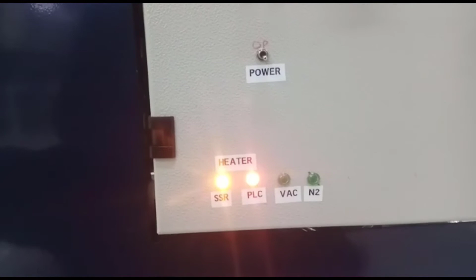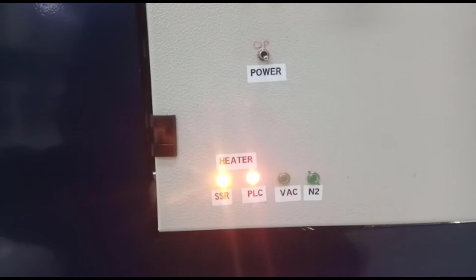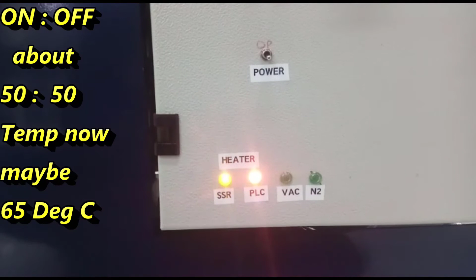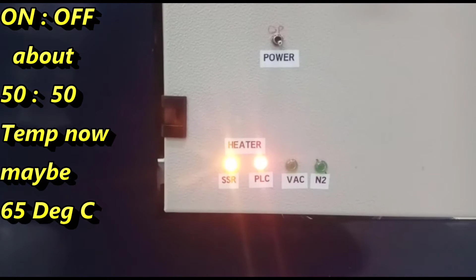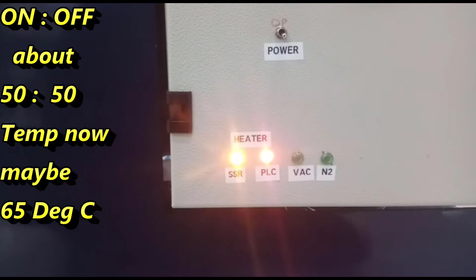This vacuum oven can be set for any temperature from let's say 50 degrees all the way to 300 degrees. It's a vacuum oven. Of course, it has the other function of infusing nitrogen, that is N2, and vacuuming in between, and those are pretty simple things to do, so it was not a big deal. But translating the ramp time and when to count the soak was the tricky part, and here it's solved in a much simpler but most efficient manner.